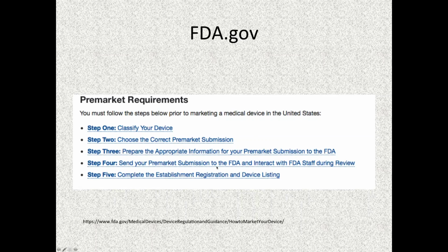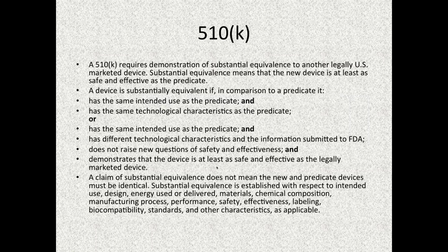Getting into classifying the device, under the 510(k) section, I'm going to go down to this line right here. It's the fifth bullet point. It has the same intended use as the predicate. This is where people get hung up. The 510(k) by itself is a demonstration of substantial equivalence. Substantial equivalence means that the new device is at least as safe and effective as the predicate. It doesn't mean that it's equal to. It just means that you can demonstrate its safety and efficacy under the same intended use as the predicate.